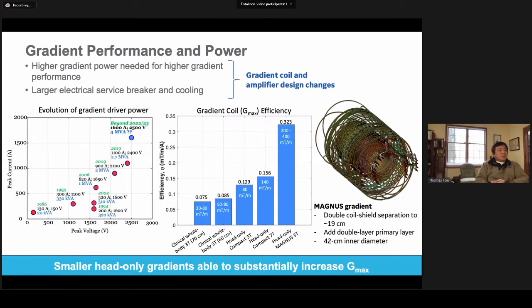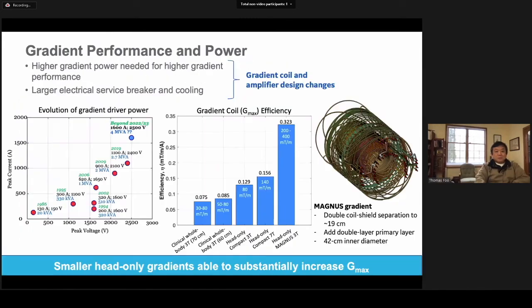So with gradient performance, there are two things you need. You need higher gradient power, or you need higher gradient efficiency. As you can see here in this chart, the gradient power has risen quite dramatically since the early days of MRI. They started with about 20 kVA of peak gradient power, and we currently have in clinical systems about 2.7 MVA of power, perhaps rising to maybe 4 or 5 MVA in the future.